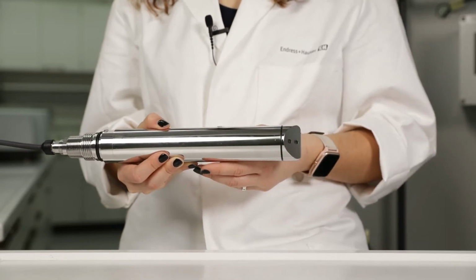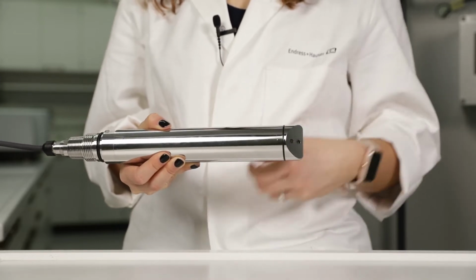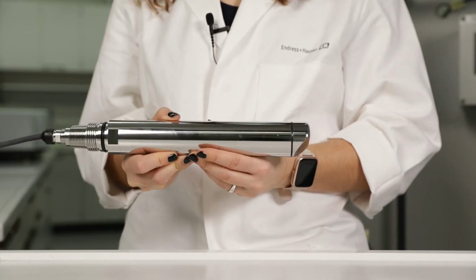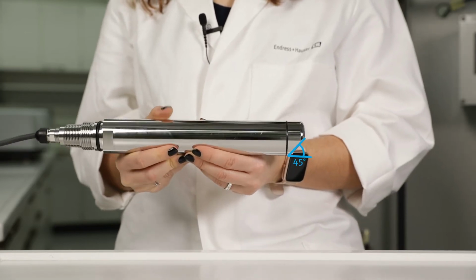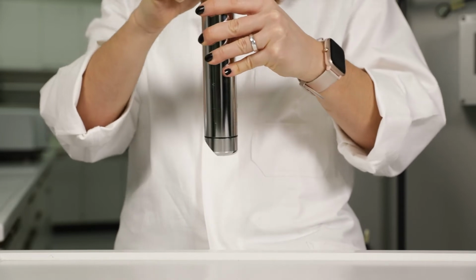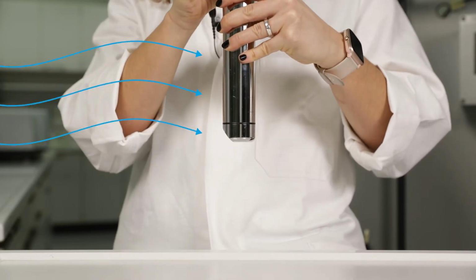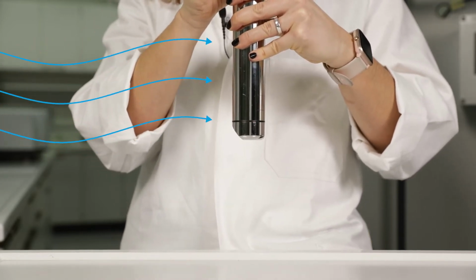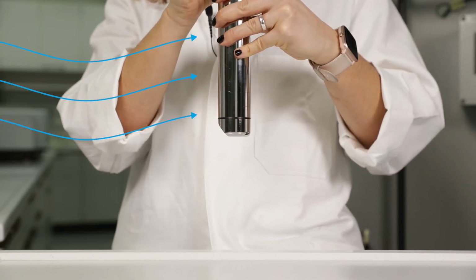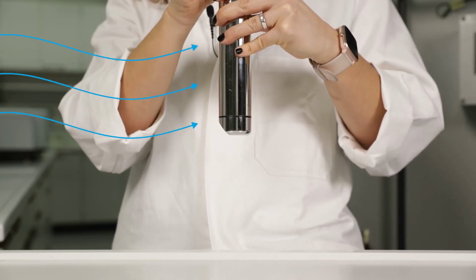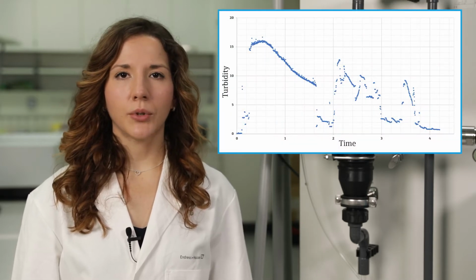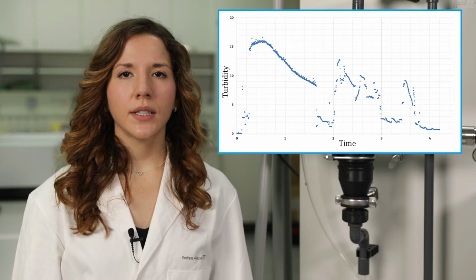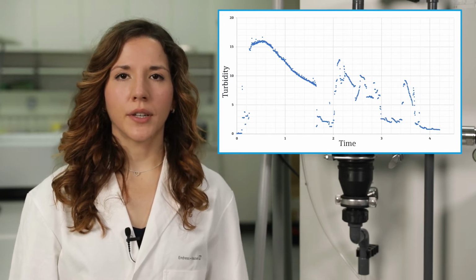The sensor head contains the measuring components and is angled by 45 degrees. This has the advantage that the sensor can be installed straight into the process and the flow automatically cleans the sensor head to a certain degree. This self-cleaning effect works best when the sensor is directed against the flow. If, however, the measured values become unstable or start to drift, as in this example, it is time to actively clean the sensor. This can be done manually or automatically.